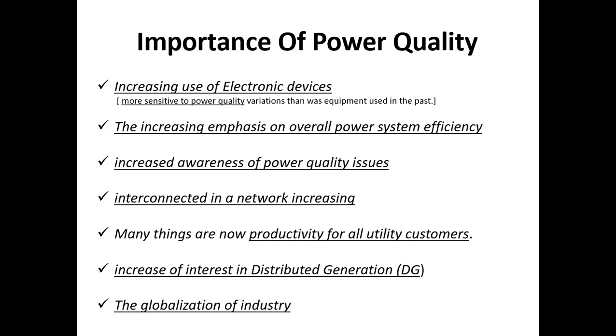Again, because of this power quality, if the voltage stability is not there, if you are not getting a pure sinusoidal waveform, if you are not getting a pure current waveform, if the current harmonics are there, if the short duration and long duration voltage variations are there, then that hampers the power system efficiency. So that's why we need to take a good, deep look as far as power quality is concerned.